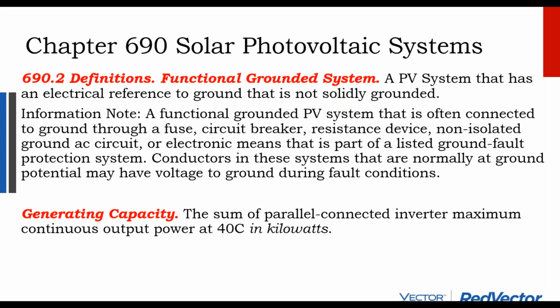I think the first, right off the bat, we get into definitions and we get this really confusing term of functional grounding. It says, a functional grounded system is one that's connected to the ground through a fuse, a circuit breaker, that is part of the listed ground fault protection system. Conductors in these systems that are normally at ground potential may have voltage to ground during fault conditions. It's kind of a confusing term and definition.